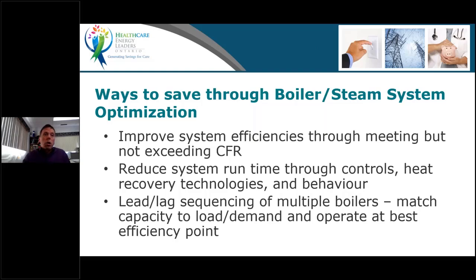So what you want to do when you want to improve your efficiency, like I said, is minimize waste. First thing, what is your CFR? What's your current facility requirements? Are you overheating spaces? Are you allowed in some spaces to have setbacks? That directly links to your boiler plant. So obviously, this is the first step that you need to do. Making sure also that your controls are running properly. Wherever you have heat recovery possibilities, you try to take advantage of that.